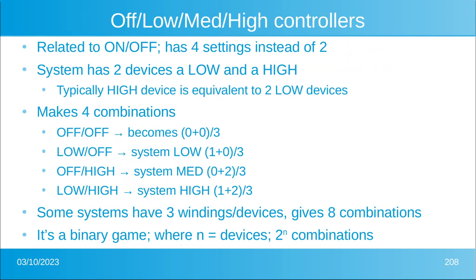Related to on/off controllers are controllers that offer off, low, medium, and high — essentially the same concept but with four settings instead of two. The system has two devices: a low and a high, where the high is equivalent to two lows — very binary. With two devices you get four combinations; with three devices you get eight. In general, if you have n devices you get 2-to-the-n combinations.